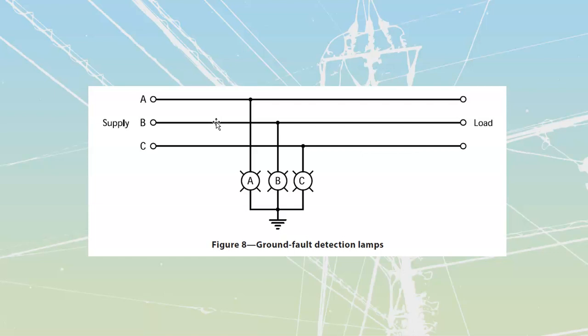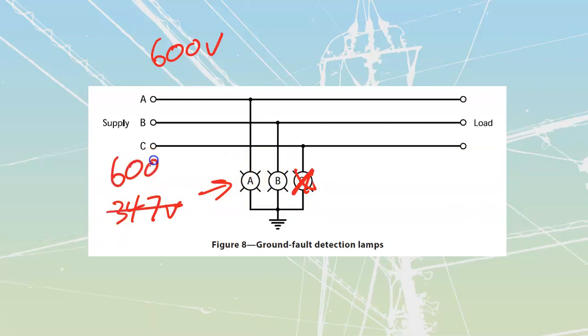In some cases, that works out fine when we have things like a 600 volt system. Perfect. I can get lights that are going to be rated up to 600 volts, as well as they're going to operate at 347. Normally, if there's no ground on the line, all of these are going to be operating at 347 volts. But then if there is a fault on the line, one of these is going to go dark and the other 2 are going to go brighter because their voltage is going to change to 600 volts.